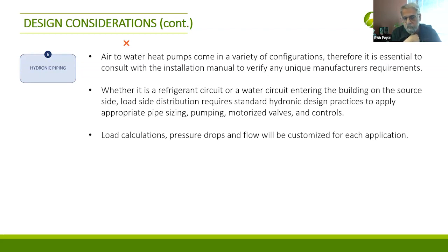As I said in the beginning, I probably went through it pretty quickly. Generally speaking, there's 2 kinds of air-to-water heat pumps. One is called monoblock. Basically, the refrigerant system in all heat pumps, in the monoblock case, that refrigerant system is doing its transfer to the water, transferring the heat to the water, all in that one outdoor unit. And so by the time it's done, all you've got to do is take that water and transfer it into the building, right? Other units are split, and they'll have an indoor unit and an outdoor unit that are married to each other by refrigerant lines. The refrigerant circuit in those cases is extended into the house, and then it does the transfer to the water inside the house.